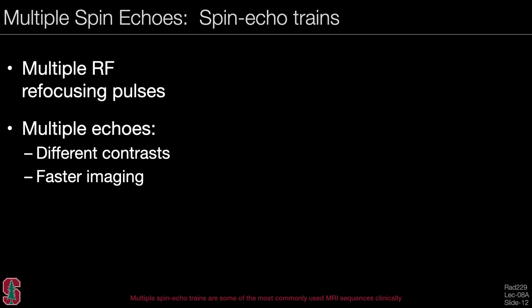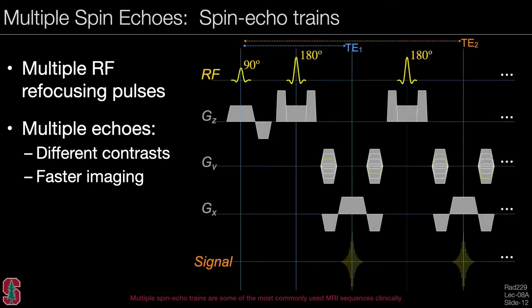We can also use multiple spin echoes in what are called spin-echo trains, using multiple RF refocusing pulses to produce multiple spin echoes. We can use these to obtain images with different contrasts based on different echo times, or combine all the echoes into a single image and acquire the image much faster. A spin echo train sequence has an excitation, a refocusing pulse, and echo time TE1, with additional refocusing pulses producing additional spin echoes at TE2 and beyond.